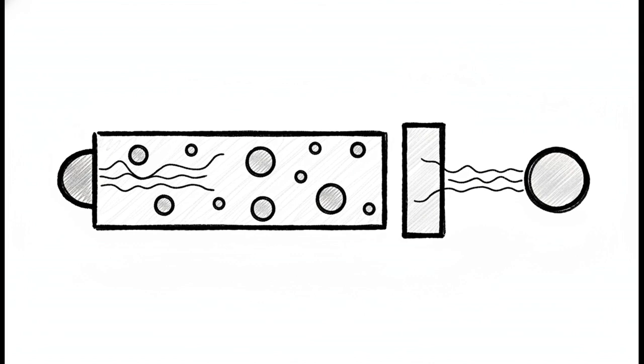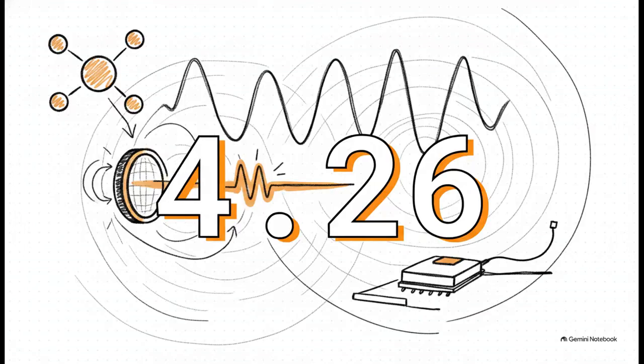At the far end of the tube, an optical filter blocks absolutely everything except the specific light that CO2 interacts with. The detector then just measures what's missing. The more light missing, the more CO2 is in the room. And get this, the exact specific wavelength of infrared light that CO2 molecules absorb: 4.26 microns. That is the magic number.